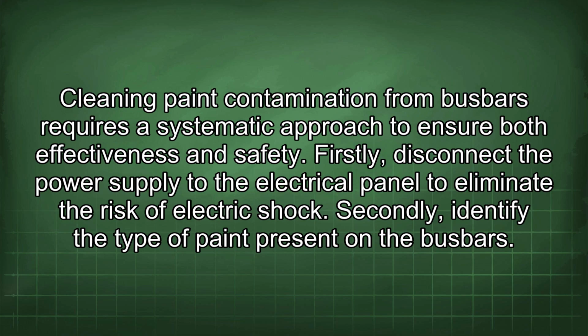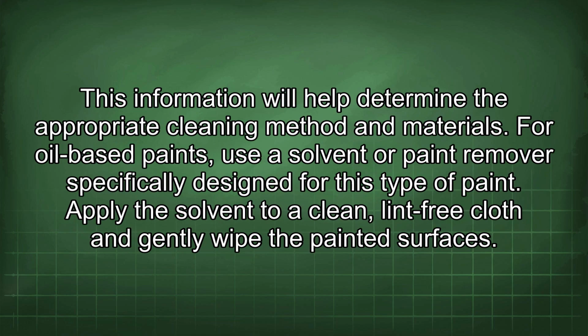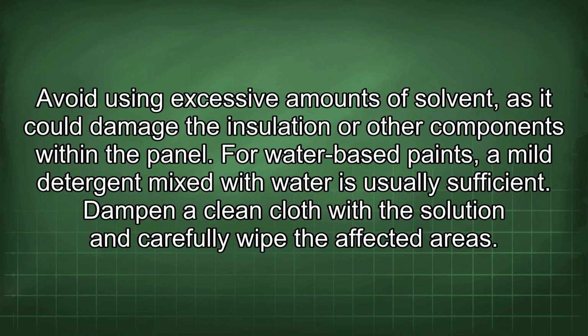Firstly, disconnect the power supply to the electrical panel to eliminate the risk of electric shock. Secondly, identify the type of paint present on the busbars. This information will help determine the appropriate cleaning method and materials. For oil-based paints, use a solvent or paint remover specifically designed for this type of paint. Apply the solvent to a clean, lint-free cloth and gently wipe the painted surfaces. Avoid using excessive amounts of solvent as it could damage the insulation or other components within the panel.